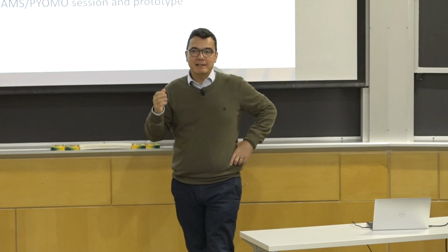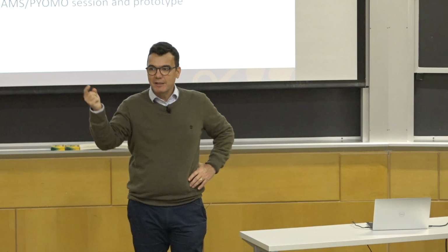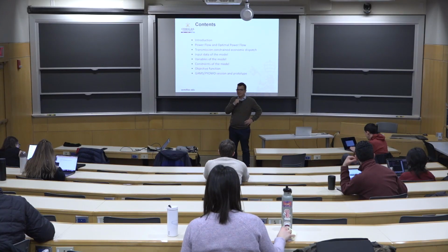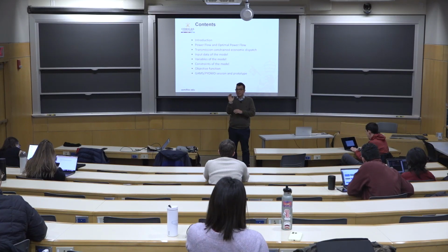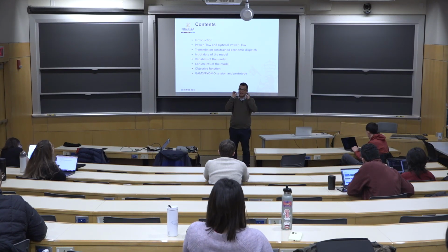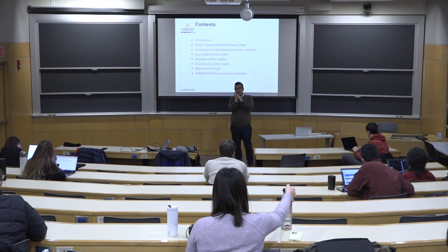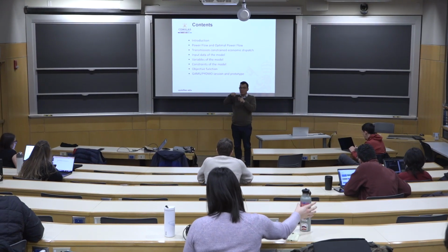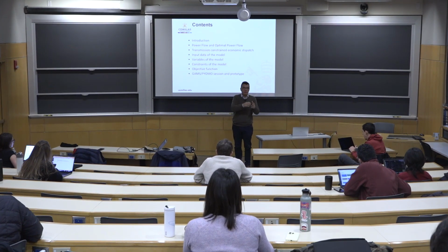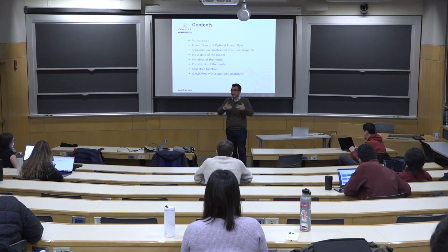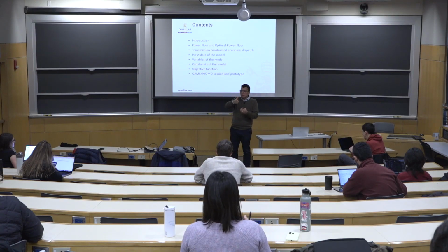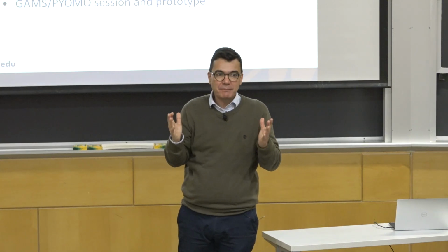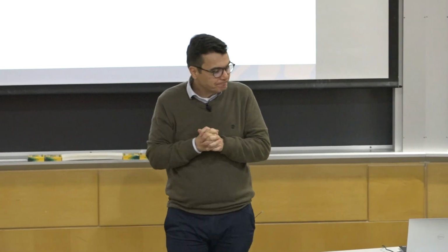A phasor is like an imaginary number that is rotating at the same frequency as the grid. And all these phasors that are rotating, if you have, let's say, a snapshot, you could compare the angle of these imaginary numbers with respect to a given reference. So this is why we need to establish an angle reference in the network, which in the time domain means that if we have a sinusoidal wave, where we start counting, where is the zero. This is basically what we have.